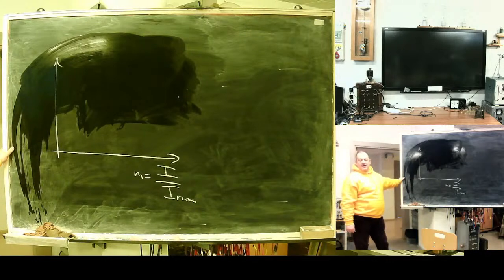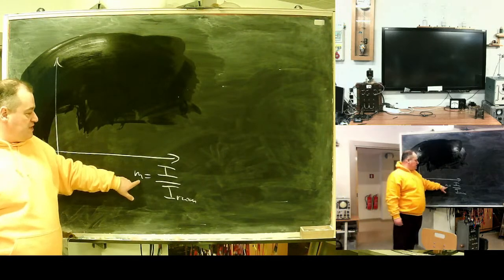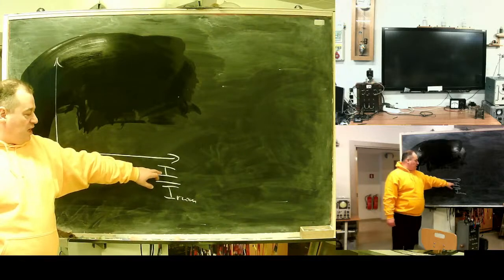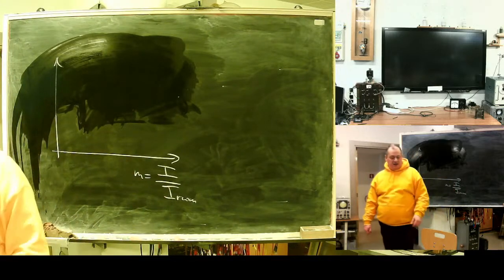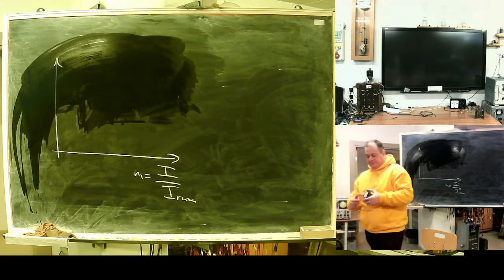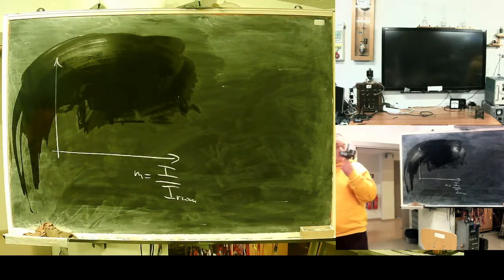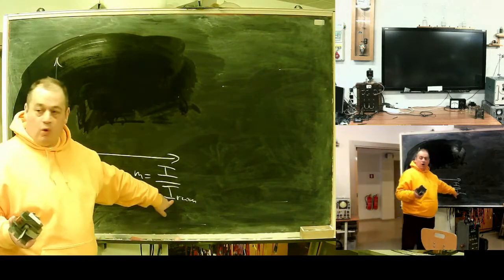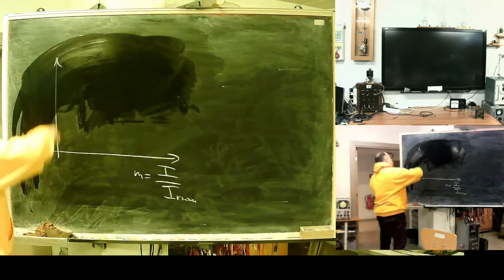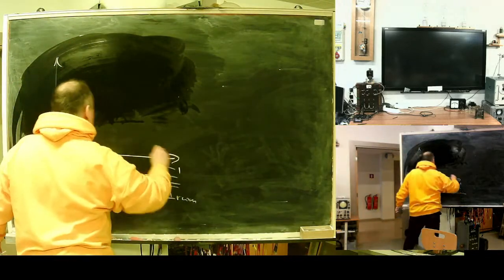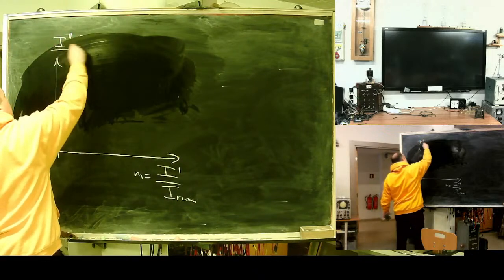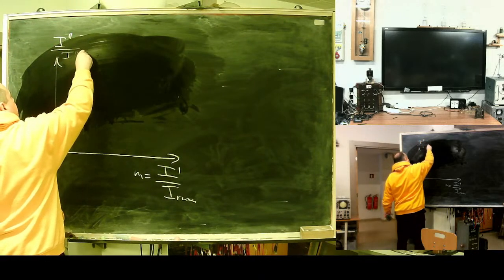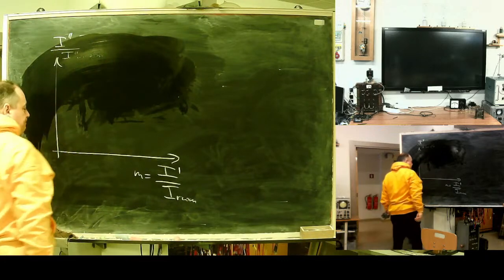What's the meaning of nominal in Latvian? Rated. So M is the ratio between the real current and the transformer's rated current. For example, this one, 200 amps, so here should be 200. And this one will be the primary current. Secondary is here, 5 amps.